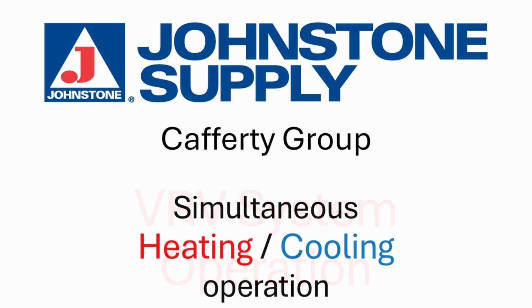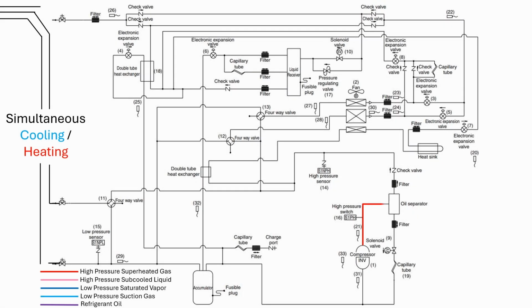Presents VRV System Operation. This system is in simultaneous heating and cooling modes. As the refrigerant leaves the compressor, it is in a high-pressure, superheated vapor state. Its first stop is the oil separator.